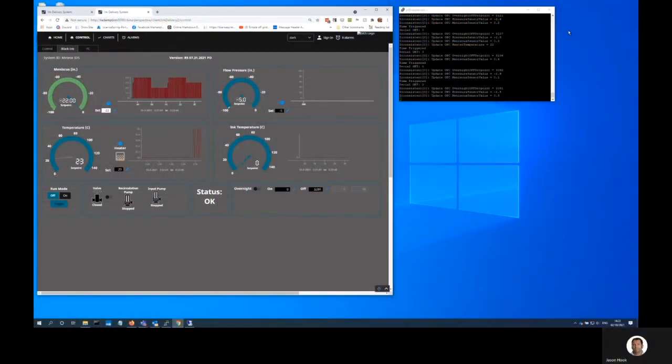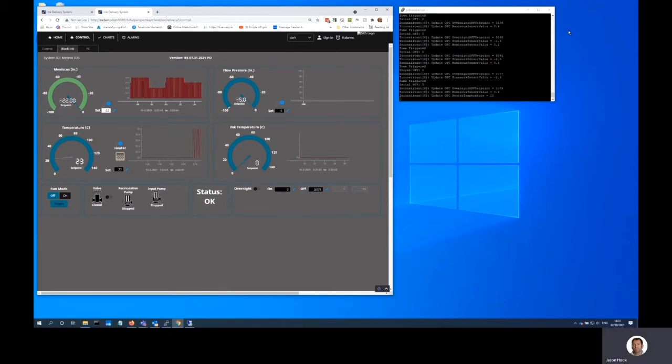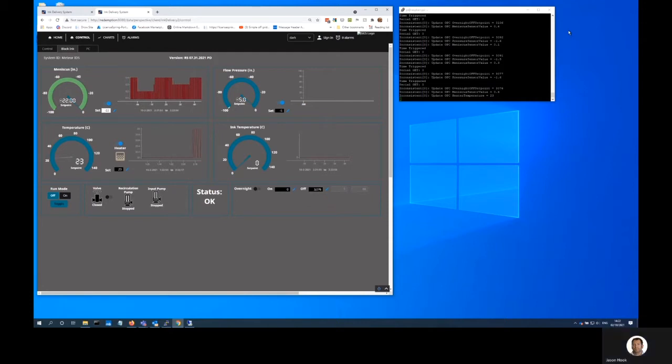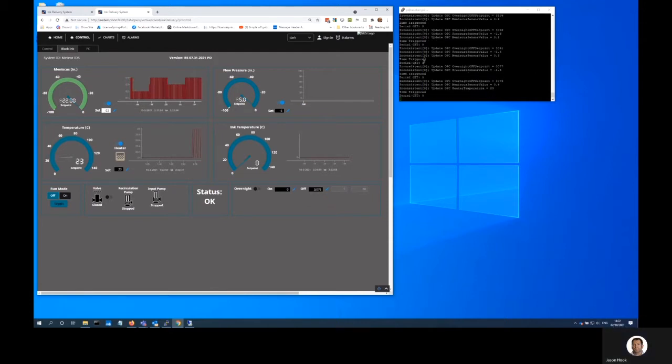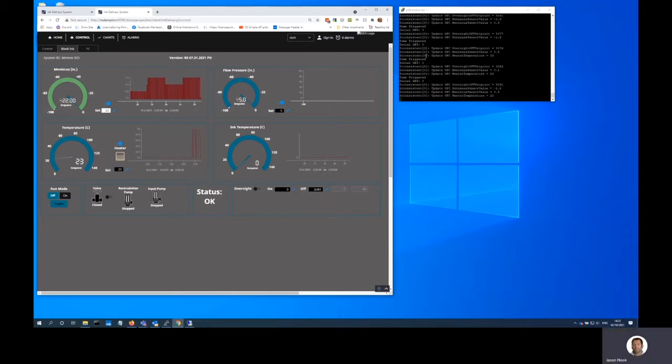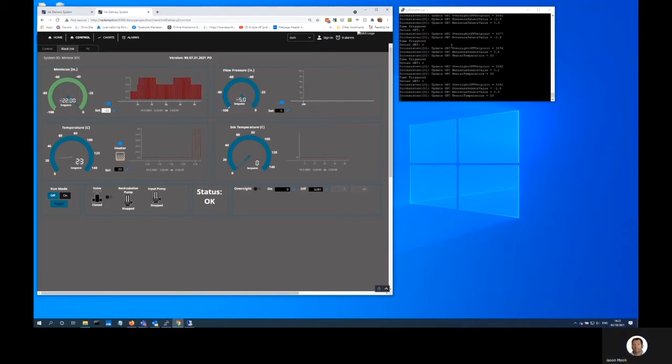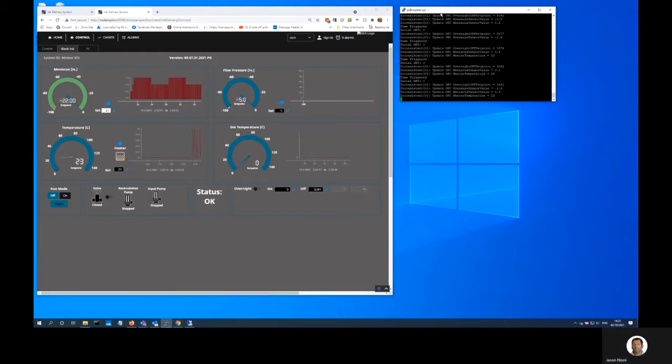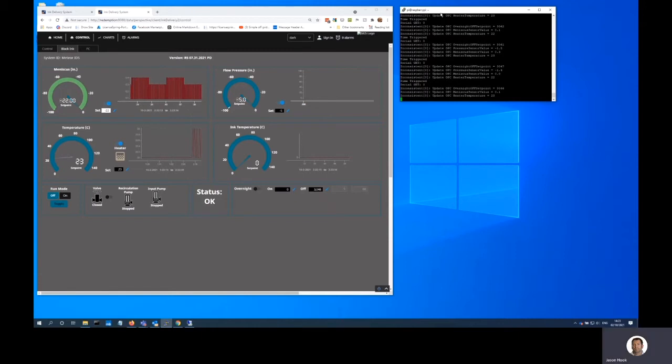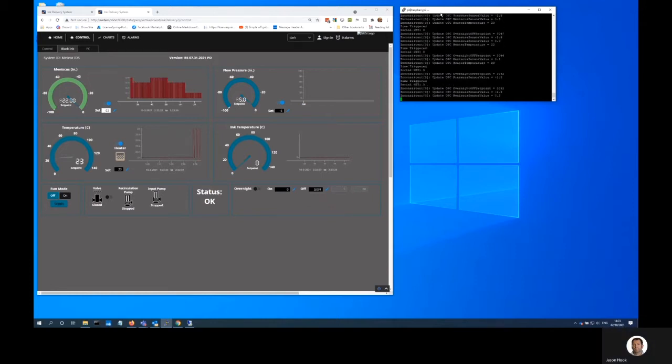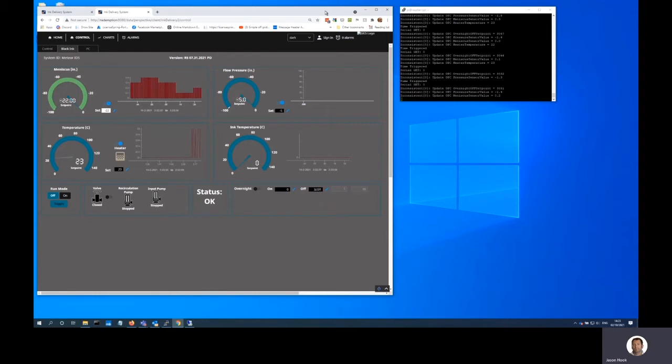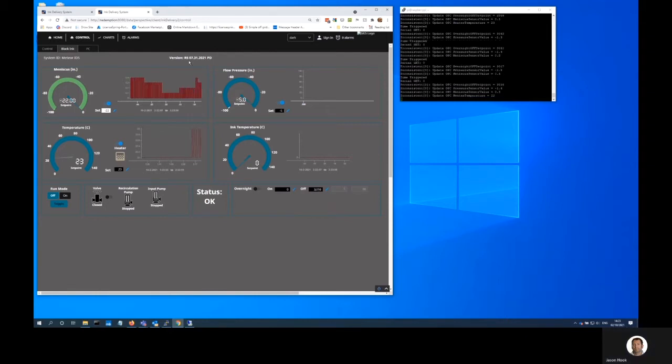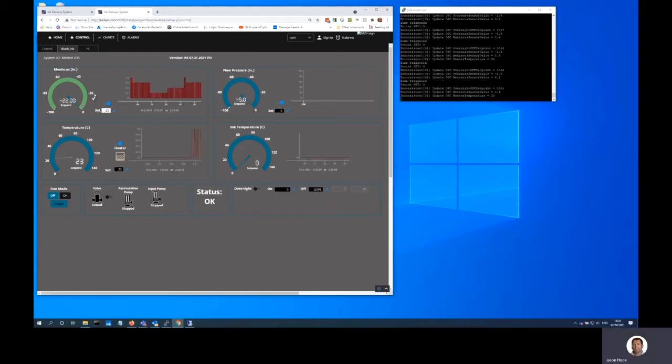In this demonstration, we're looking at an ink delivery system, which is connected to an OPC UA server running on a Raspberry Pi. And we're receiving information about the ink delivery system in the SCADA application, which is displayed in the web page on the left hand side of the screen. Data is coming from the ink delivery system and being displayed currently in the form of gauges and graphs. Where we're using graphs, data is being recorded separately in a database and can be retrieved later for further use. We have bi-directional control of the ink delivery system, allowing us to use the buttons that we've designed into the application to turn the machine on, to open and close valves and affect the temperature of the heater. Some static data is available in terms of the machine name and the version. And we're receiving information from various parts of the ink delivery system, meniscus, flow pressure, temperature, ink temperature. And the data is coming back from the ink delivery system in real time.